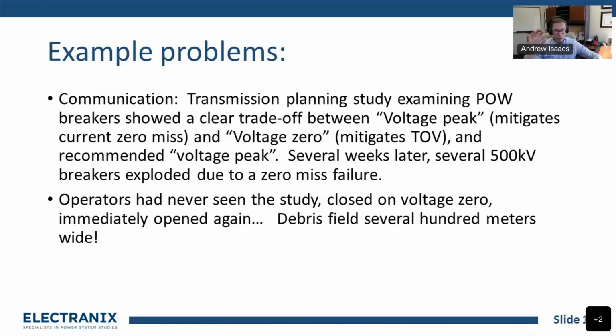So they showed this trade-off, and a couple weeks later, after the study was finished and understood, a couple of 500 kV breakers exploded. Operators who were controlling this scenario closed on a voltage zero and then immediately opened again, had a zero miss on the breaker, and there was a huge debris field. This is an example where if we'd just had a conversation about that study result, it would have been very, very good.